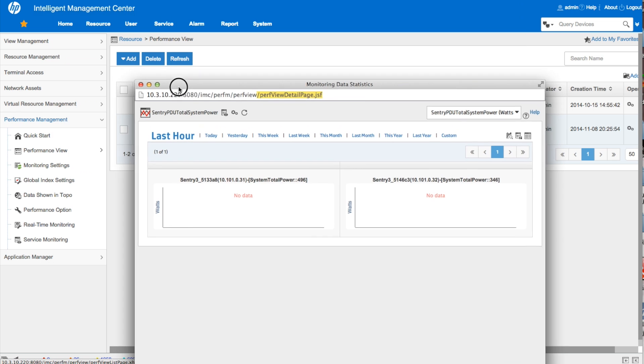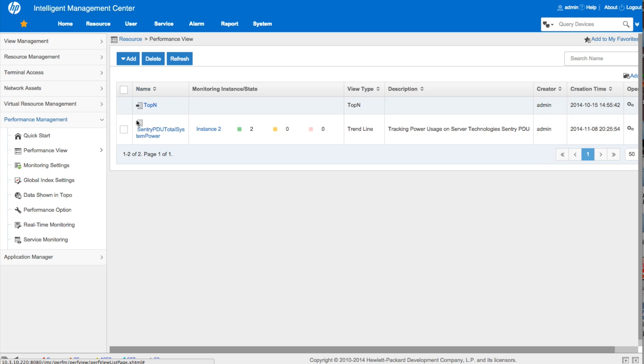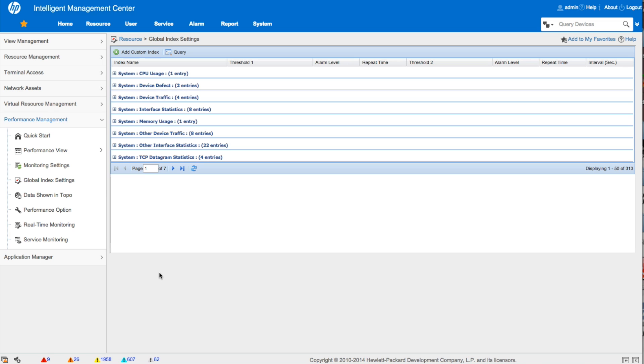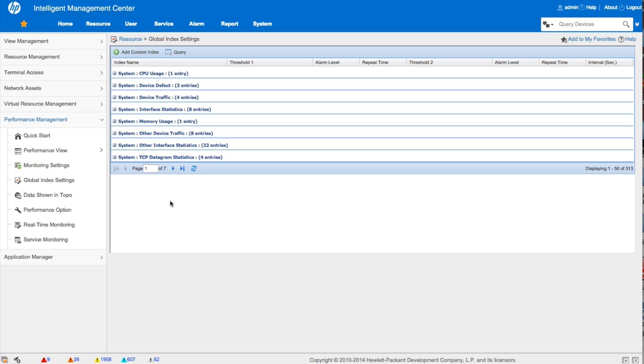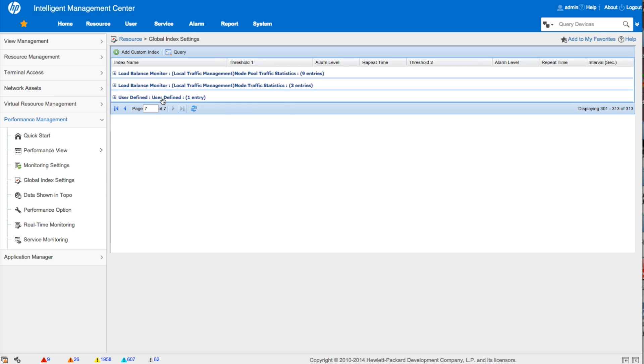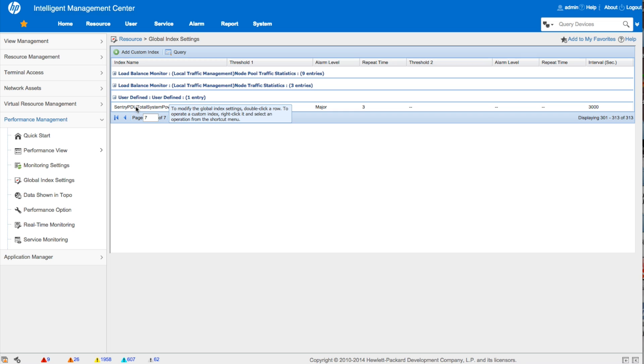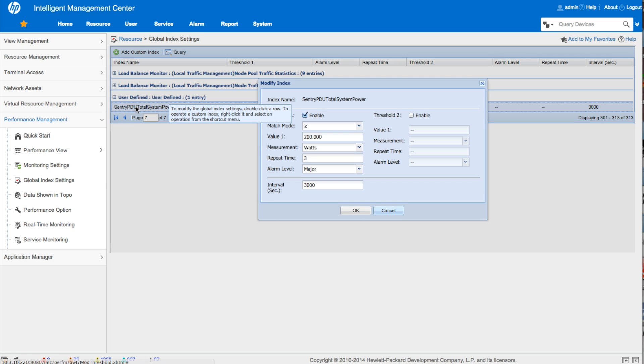I'm just going to click on the button here and look at that. We have no data. So that's probably, I'm thinking about this now. That is because I set the polling period to be something like 4,000 seconds. So we're going to go fix that now. So this is a good lesson in when you do things on the fly. You really have to think about them. So I'm going to go back to the other page here. User defined. And I will show you guys why we're not tracking any data yet. So you can see here the interval is 3,000 seconds. So we're only going to poll this every 50 minutes. You do not want to sit here and watch this video for 50 minutes waiting for that number to come up.